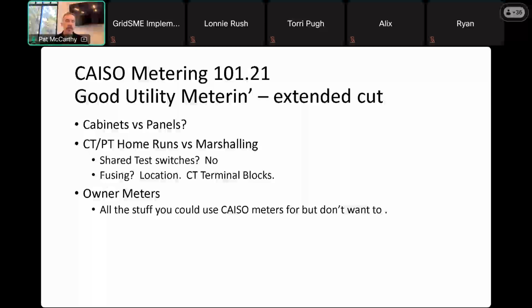CT/PT home runs straight into a cabinet, which is not accessible, so the wiring is not accessible anywhere else. What can you most reasonably do? You can put your circuits in marshalling cabinets and mount your meters in panels, but keep in mind that there are audits and routine inspections, and these things can come up.